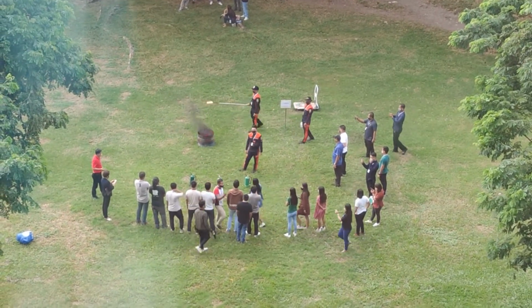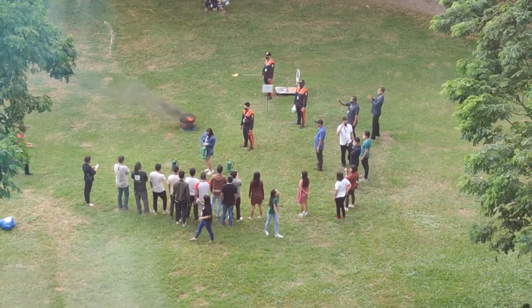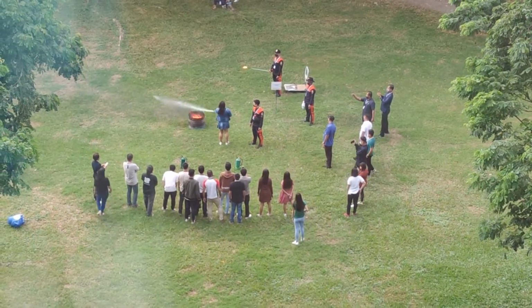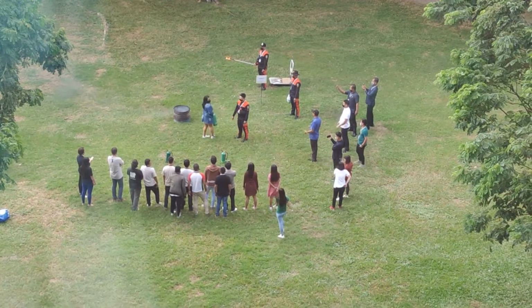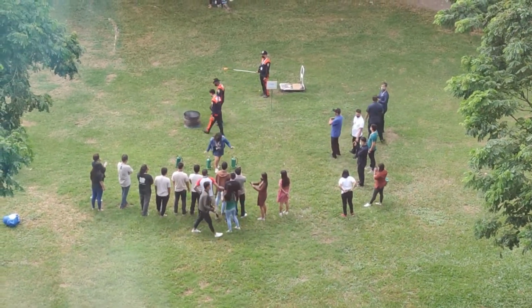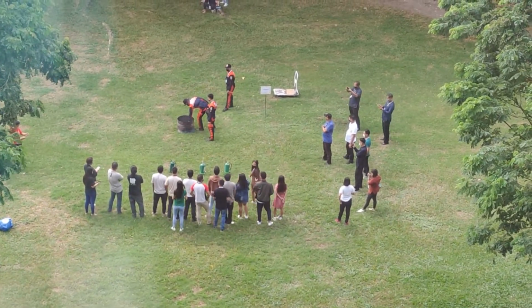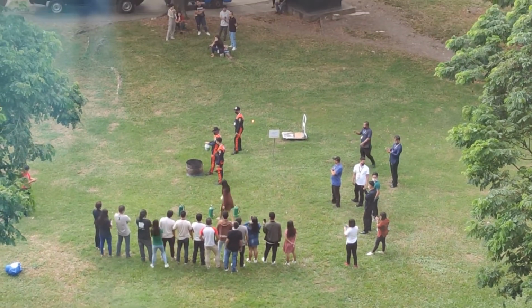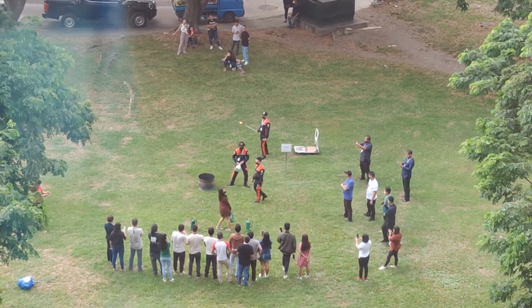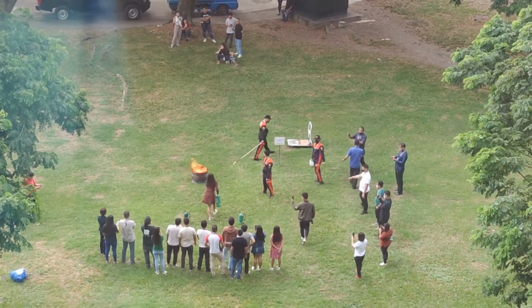Fire extinguishers manufactured with non-cylindrical pressure vessels also exist but are less common. There are two main types of fire extinguishers, stored pressure and cartridge operated. In stored pressure units, the expellant is stored in the same chamber as the firefighting agent itself. Depending on the agent used, different propellants are used. With dry chemical extinguishers, nitrogen is typically used, while water and foam extinguishers typically use air. Stored pressure fire extinguishers are the most common type.